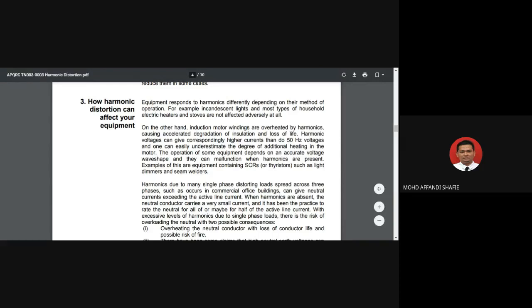So the operation of some equipment depends on an accurate voltage wave shape, and they can malfunction. Okay, the first one is heating, and then the second one is malfunction when harmonic present. So example of this equipment containing SCR, silicon control rectifier, okay, or we call it thyristor. So this is the device that we use in power electronic switching, such as light dimmer and seam welder.